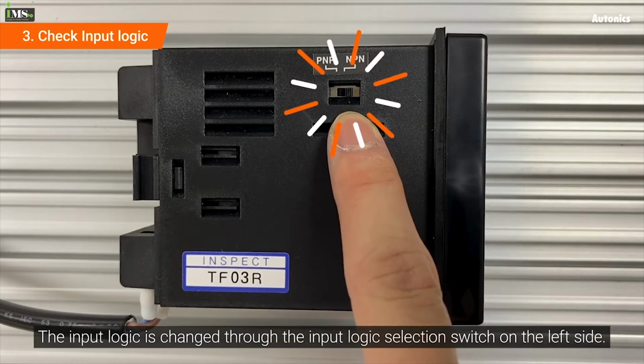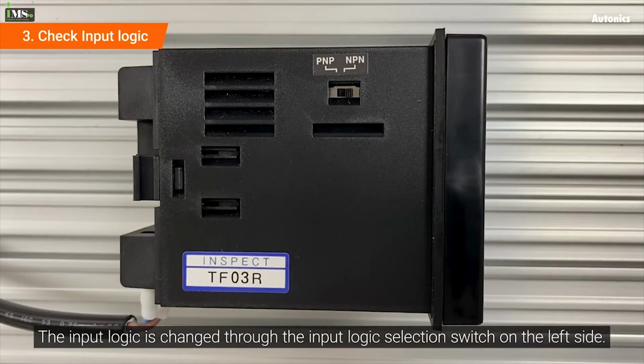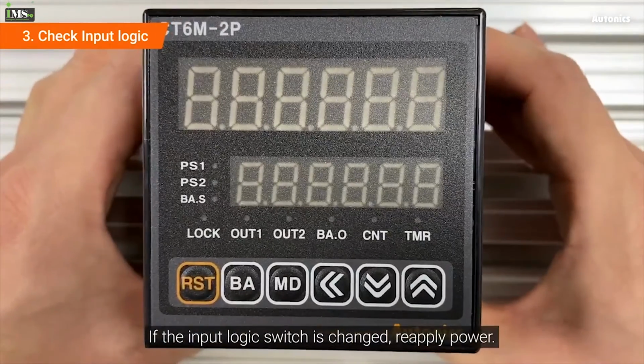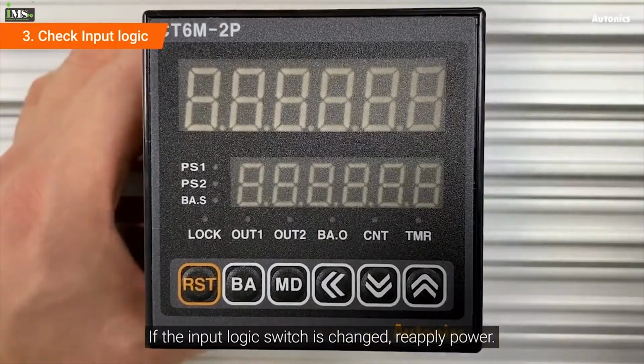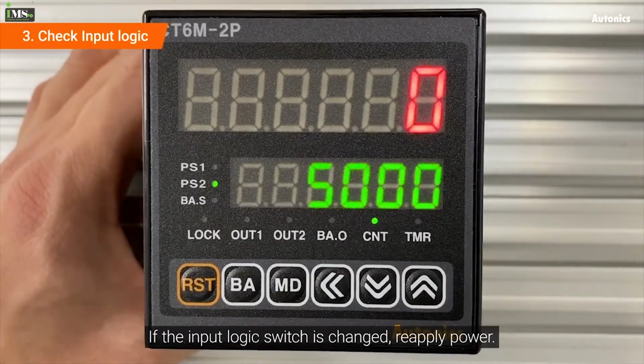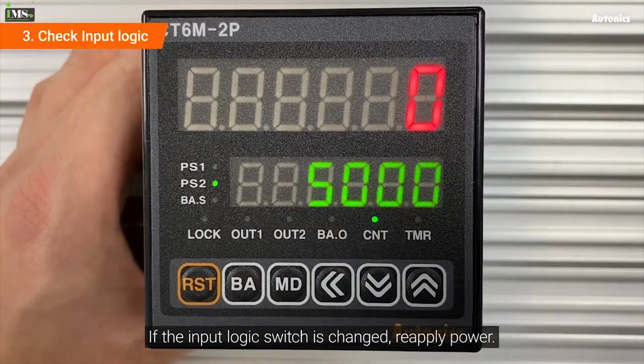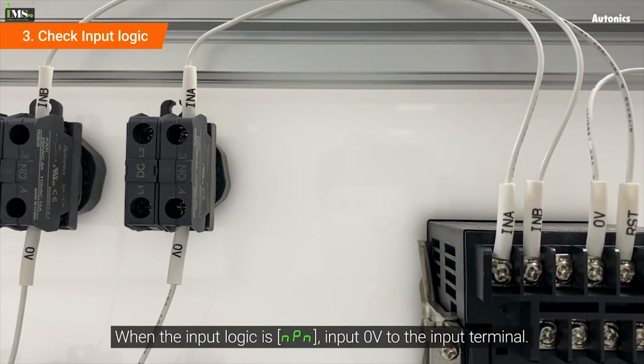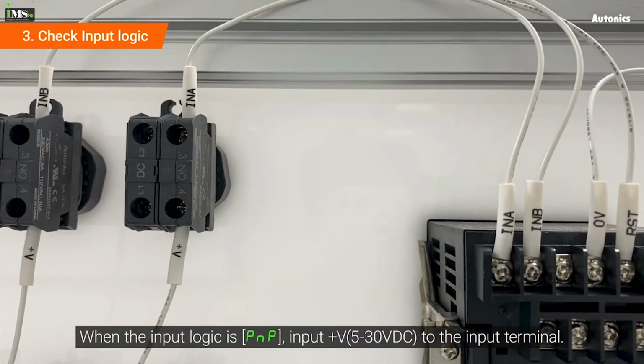The input logic is changed through the input logic selection switch on the left side. If the input logic switch is changed, reapply power. When the input logic is NPN, input 0 volt to the input terminal. When the input logic is PNP, input plus volt to the input terminal.